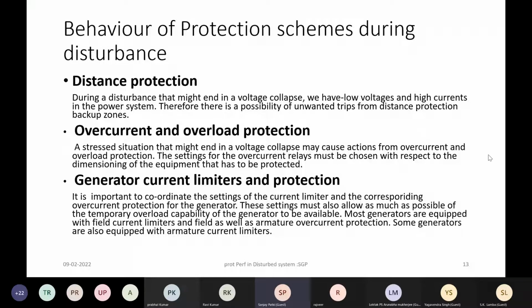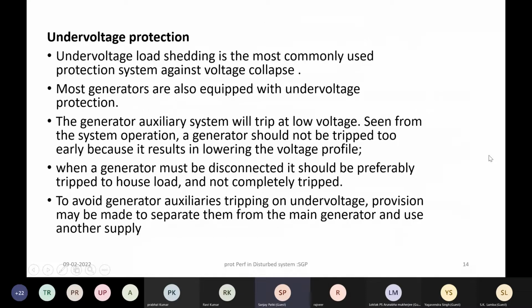Another protection which can malfunction if not properly coordinated is under voltage protection. This under voltage protection is primarily at the thermal power stations where the big auxiliaries, ID fan, FD fan, boiler feed pump, etc. are all protected with under voltage protection. And this under voltage protection on the induction motors should be set in such a manner that during a grid disturbance or fault condition, that means if there's a single phase to ground fault and a voltage dip, this under voltage protection should not operate. For a single phase to ground or double phase to ground fault, it should operate only on three phase under voltage condition.